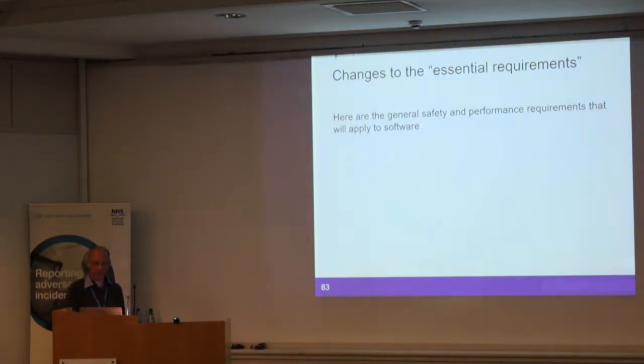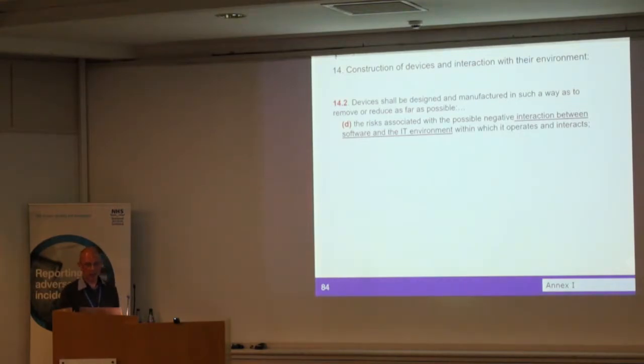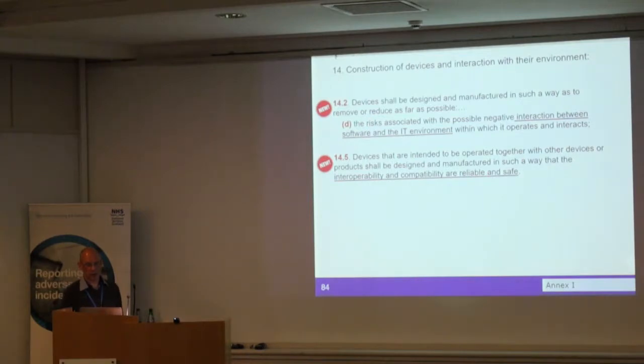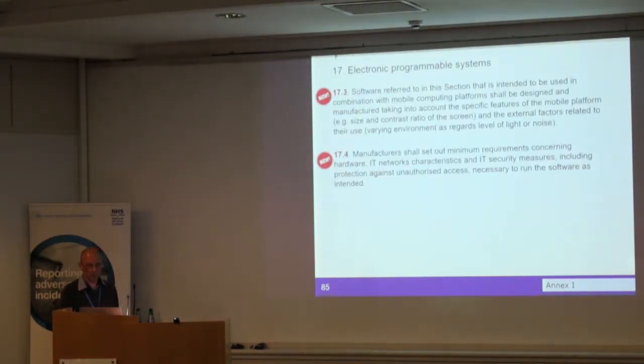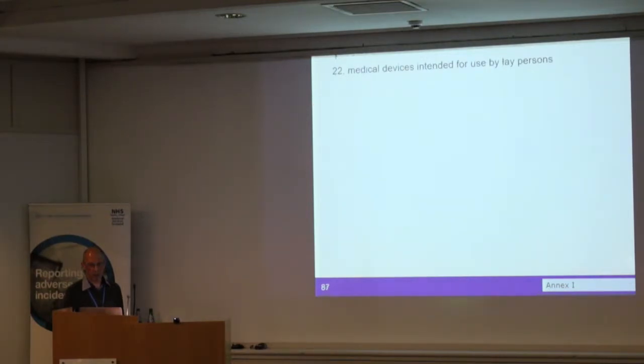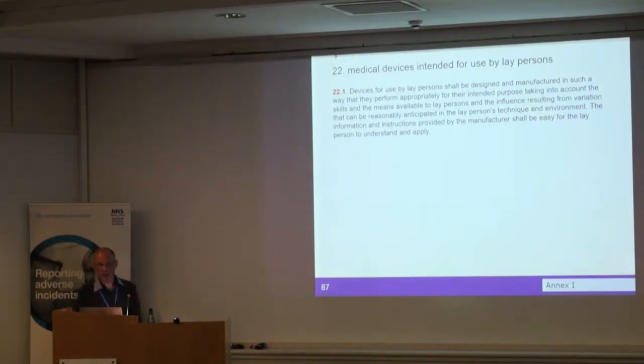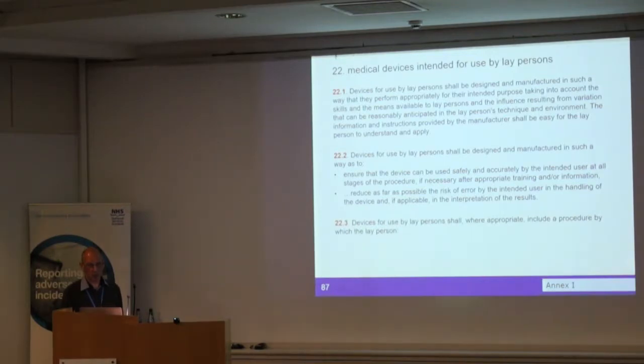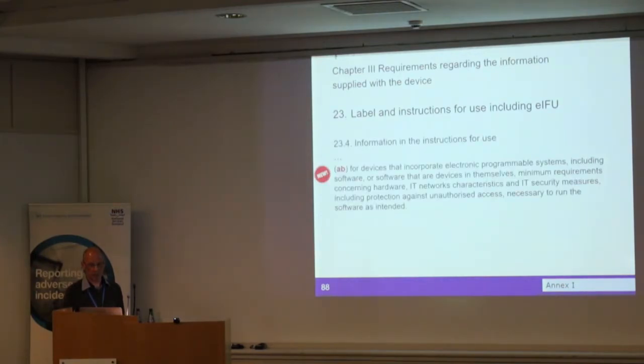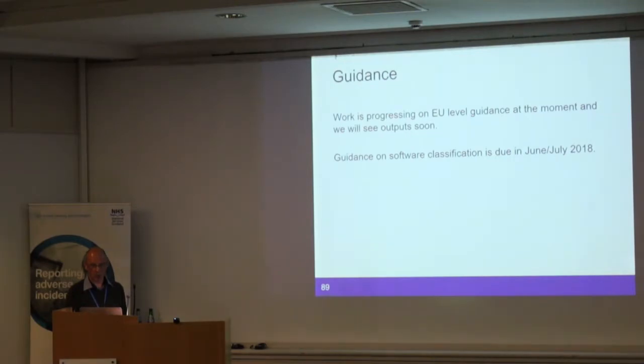There are changes to essential requirements about interaction with the IT environment, so interoperability and compatibility, and measures to prevent unauthorized access, so that software should run as intended. And there's also a huge amount of work looking at devices intended for lay persons. So there are 3 new essential requirements that are popped in. So the manufacturer, if it's intended for a lay person, then they have to consider skills, means available for a lay person, etc. Instructions for use, again, will have to include information about IT and security measures and how to run the software as intended. We're working at European level at the moment.